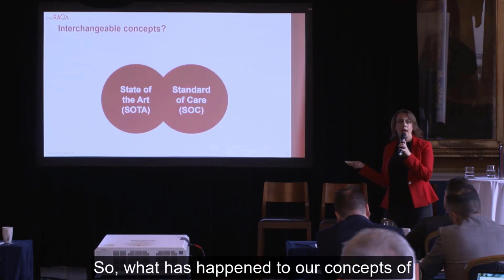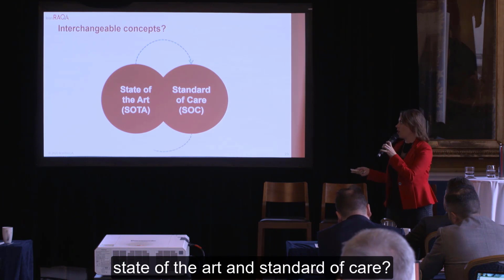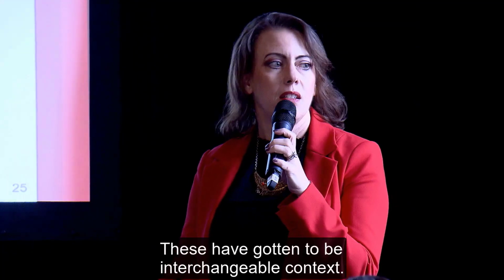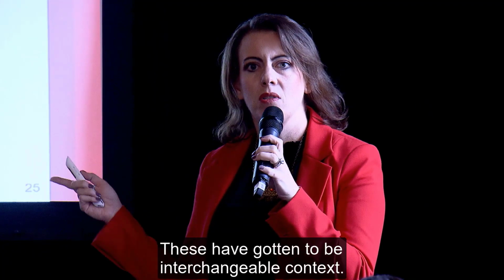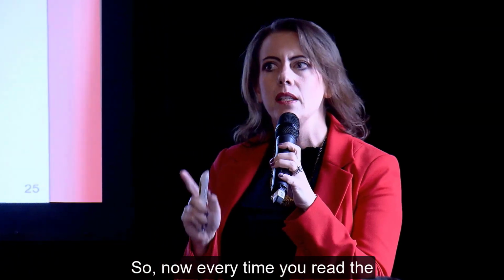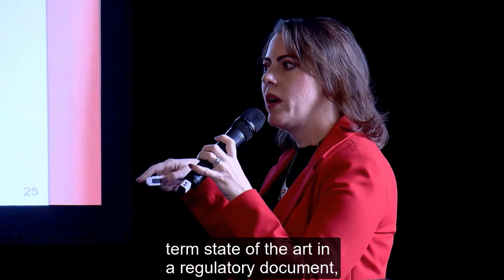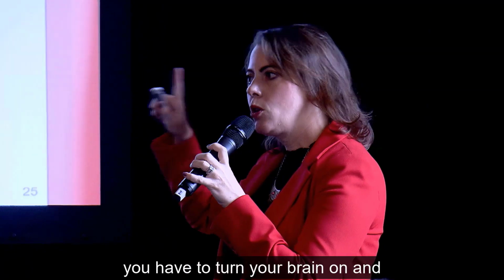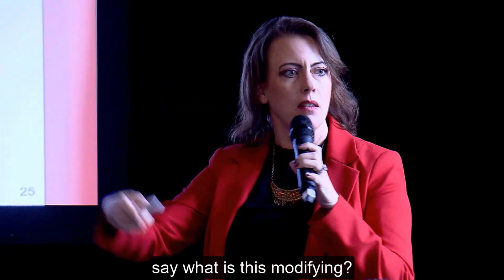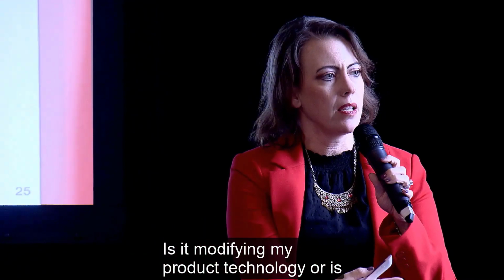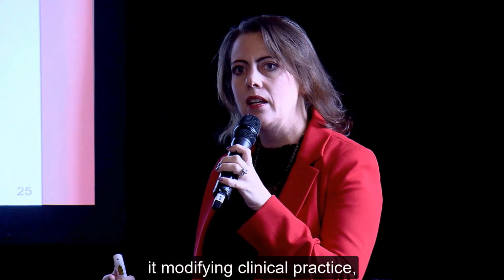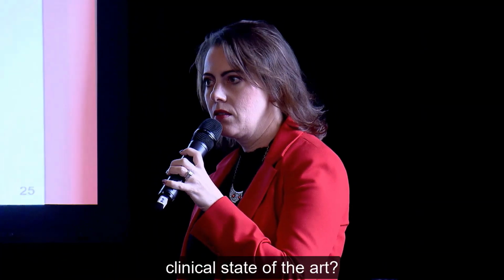So what has happened to our concepts of state of the art and standard of care? These have become interchangeable in context. So now every time you read the term state of the art in a regulatory document, you have to turn your brain on and ask, what is this modifying? Is it modifying my product technology, or is it modifying clinical practice, clinical state of the art?